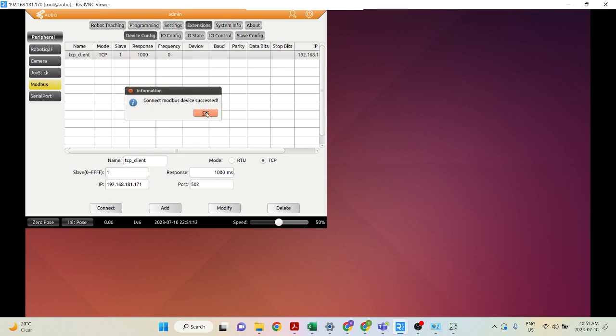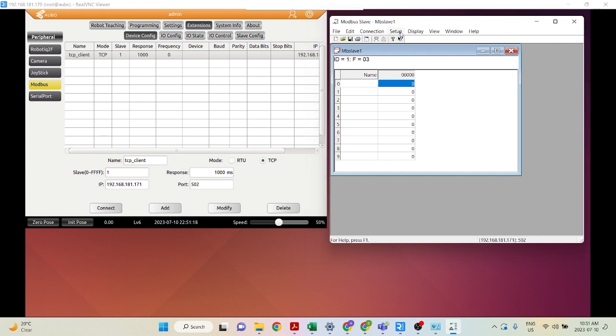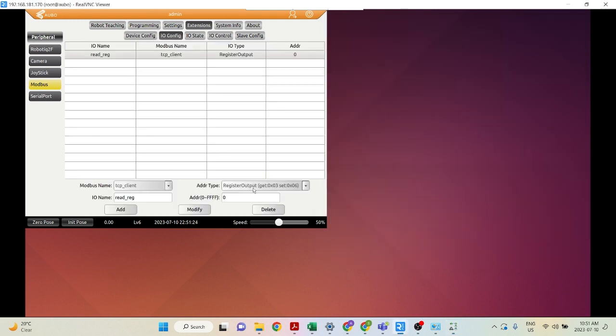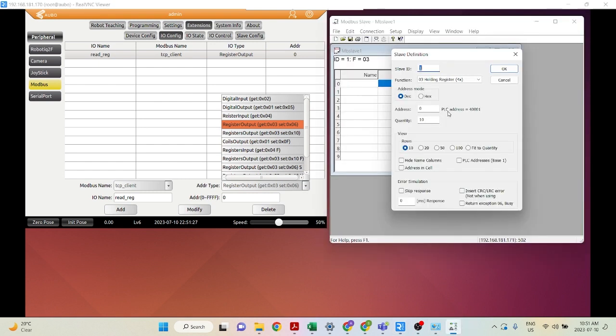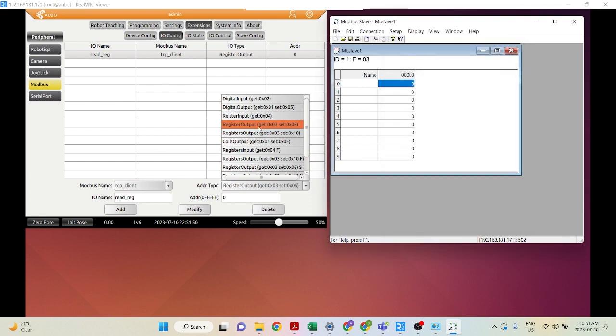Connect Modbus device success. Now let's test this connection. Go to Setup and then Definition. In our IO Config we're using register output, which corresponds to Holding Register here. Digital input corresponds to Input Status, digital output corresponds to Coil Status, register input corresponds to Input Registers, and register output corresponds to Holding Registers. Let's select Holding Register and click OK. With register output or holding register, you can both read and write.